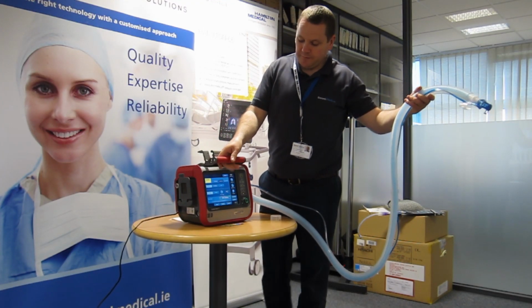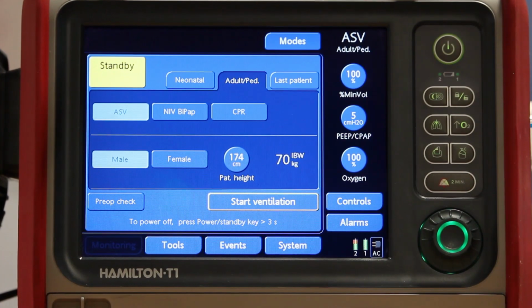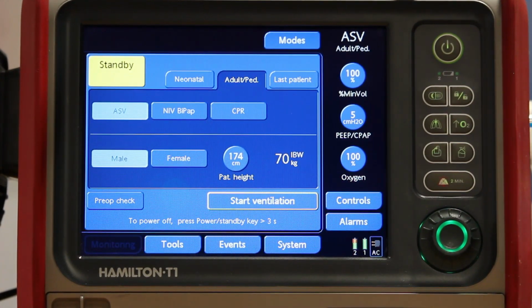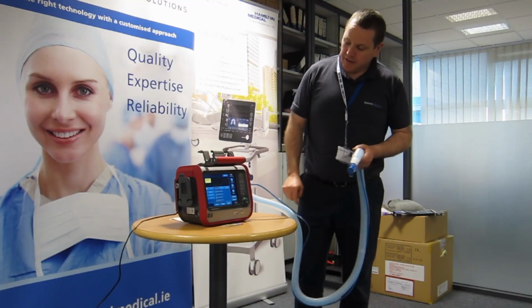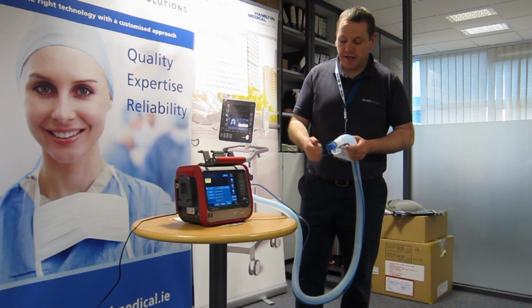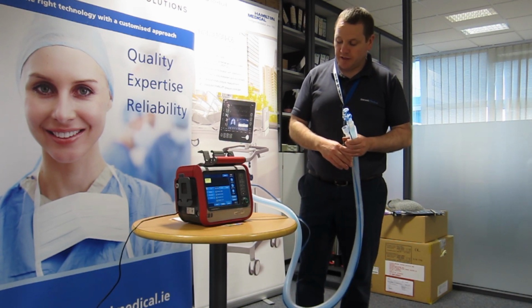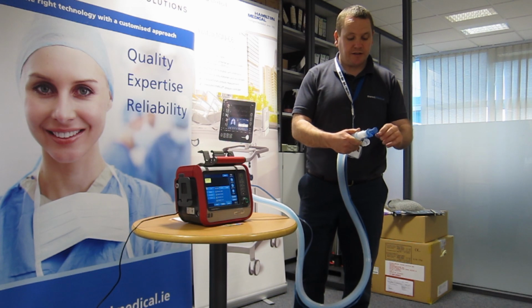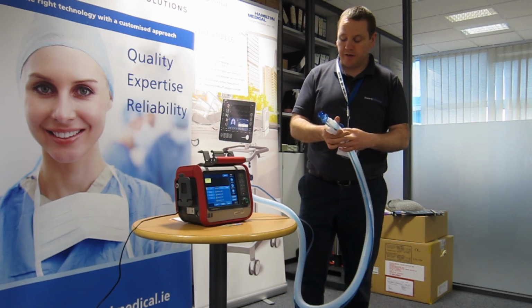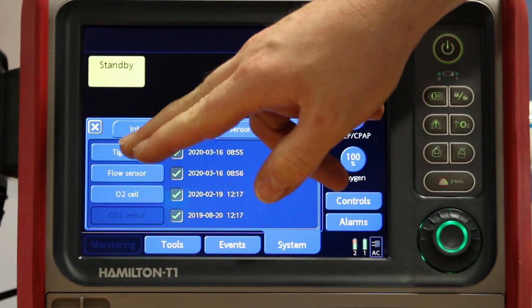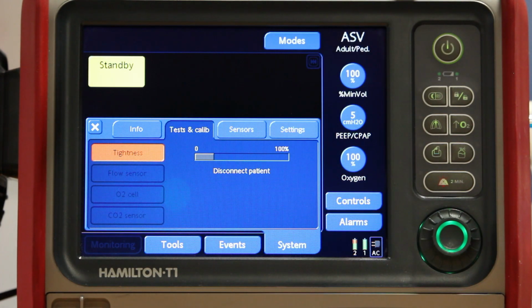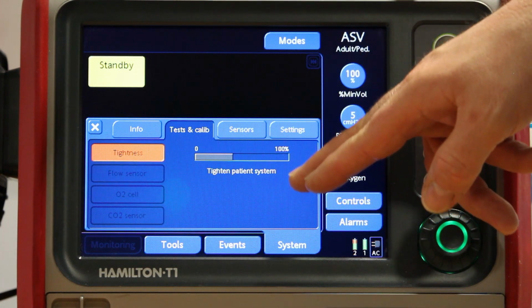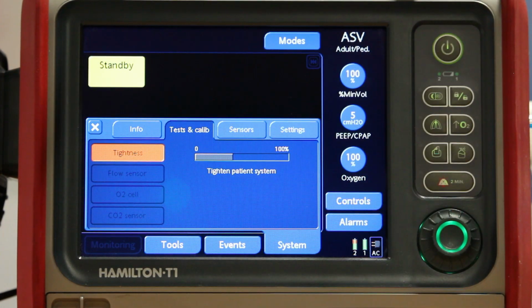So if you look here on the bottom left hand corner of the screen, we have our pre-op check button, and it's here that I'm going to test the circuit for tightness and also to make sure that the flow sensor is working. The circuit has a dust cover on, which I'm going to take off to get it ready for the testing. So the first one I'm going to do is tightness. So I hit the tightness button here. It tells me to disconnect the patient, and then it prompts me to tighten the patient's system.